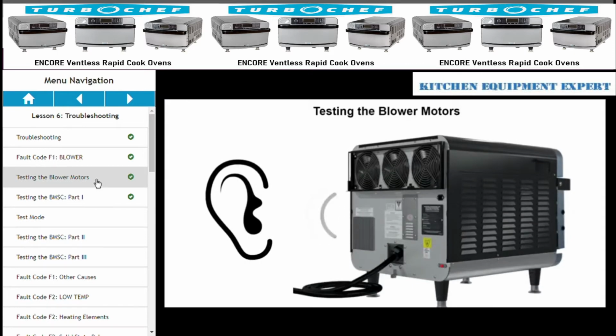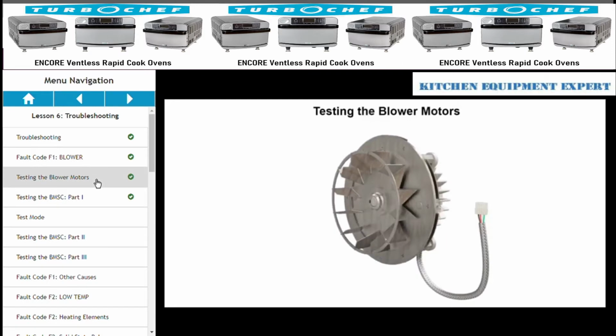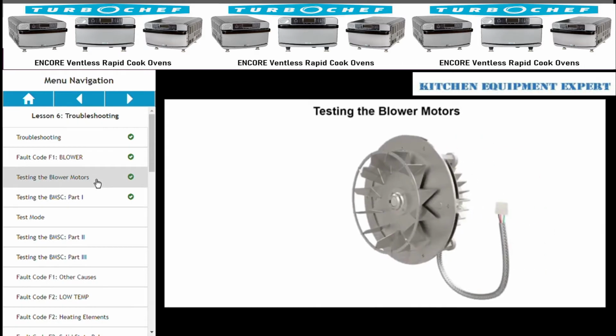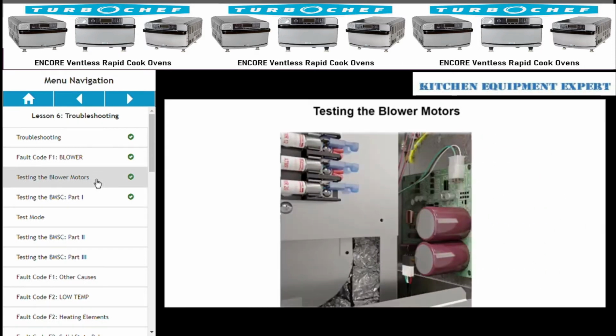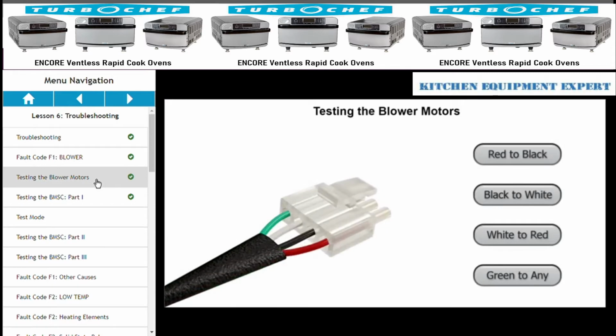If the blower seems unusually noisy, remove it and inspect it visually. Remove any debris or buildup on the fan blades. If the bearings are noisy or if the fan doesn't turn freely, replace the blower motor assembly. To check the motor electrically, at the BMSC, remove the connection to the blower motor, marked J5. Click on the buttons to test the different points.